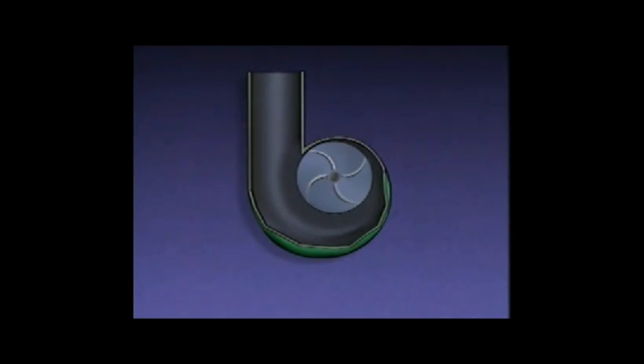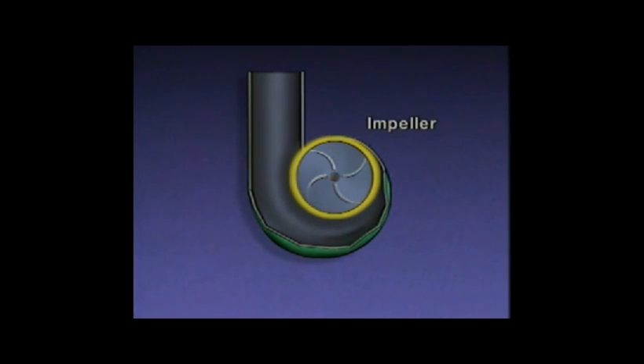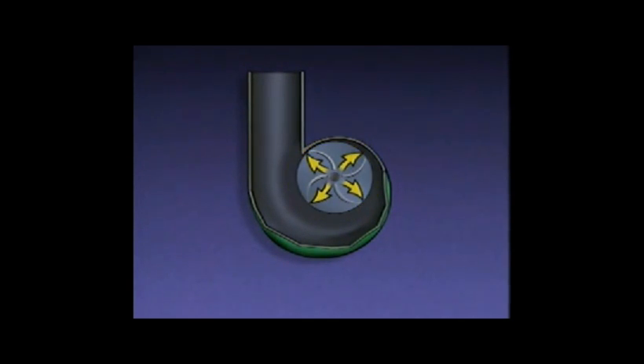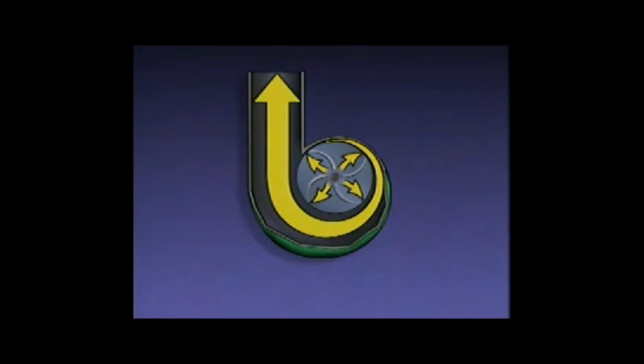Centrifugal compressors work differently. A centrifugal compressor uses a device called an impeller to spin the gas around, which accelerates or increases the speed of the gas flow. The acceleration gives the gas energy. As the gas stream flows out of an impeller, it spreads out and slows down, and as it slows down, its energy is converted into pressure.